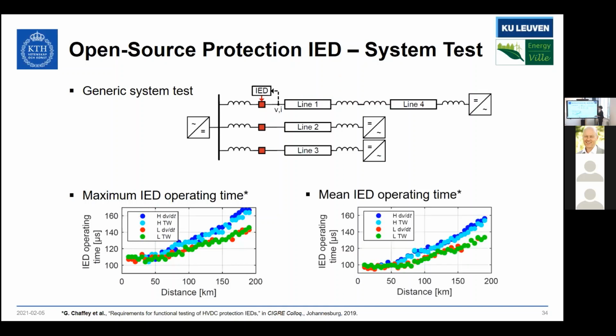This is the maximum IED operating time. Here you see the mean IED operating time. There's a 10 microsecond difference, and this is easily explained by the fact that the IED is a sampled system at 50 kilohertz with a 20 microsecond resolution, so you get a variability of plus minus 10 microseconds, which is exactly what you see here.